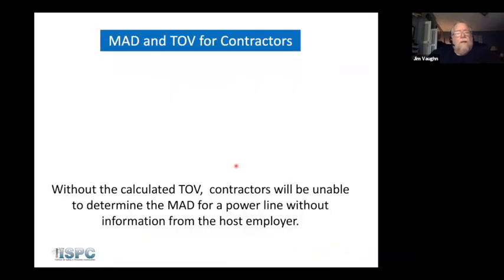So the issue for contractors, if you're a contractor out there, is that your customer is supposed to give you, remember, information in the information transfer. If you're doing transmission work, they don't have to tell you what their MAD is, but they are obligated to give you the information that you need so that you can calculate MAD for the work that you're doing. And what happens then is you go back to the calculations, or you go back to the tables that have the TOV multiplier in that table. They tell you what their calculated TOV is, and then you use the tables using that TOV.